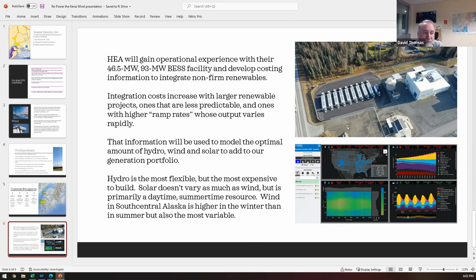So that was one big driving force behind this battery energy storage system, because it's akin to if the passengers only need 2 cabs, you keep a 3rd cab idling at all times. You're running the engine inefficiently, you're putting hours on it, you're incurring labor and maintenance, all to be ready to jump in if anything should fail. And for months of 2019, when we were islanded, we were running Bradley plus Nikiski, but also a third shaft at Bernice Lake. When we're islanded, we can burn $1,000 an hour more fuel than we will with the battery energy storage system ready to jump in. So it provides that spinning reserve in our future, where formerly we had to do that with our combustion shafts by constraining their operation.